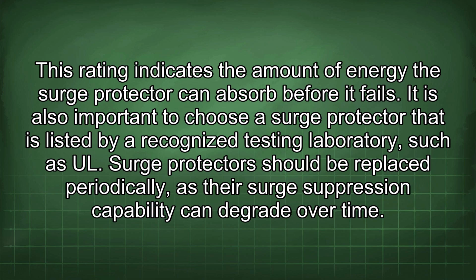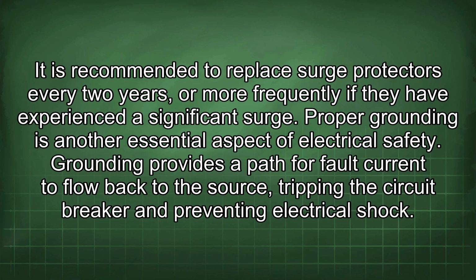Surge protectors should be replaced periodically as their surge suppression capability can degrade over time. It is recommended to replace surge protectors every 2 years or more frequently if they have experienced a significant surge.